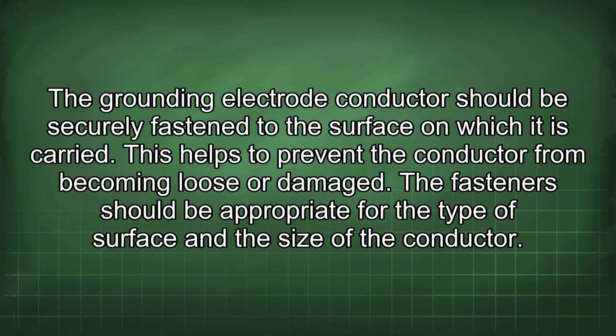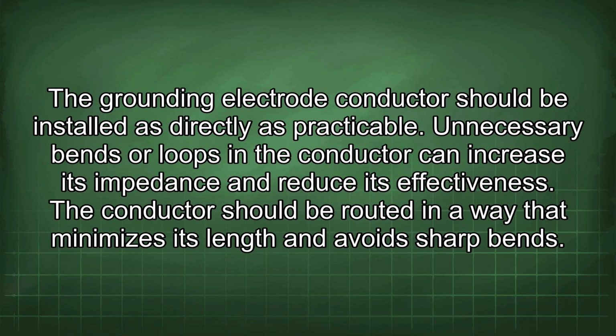This helps to prevent the conductor from becoming loose or damaged. The fasteners should be appropriate for the type of surface and the size of the conductor. The grounding electrode conductor should be installed as directly as practicable. Unnecessary bends or loops in the conductor can increase its impedance and reduce its effectiveness. The conductor should be routed in a way that minimizes its length and avoids sharp bends.